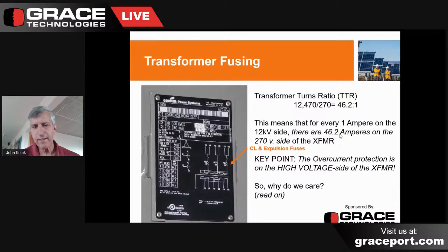Then there's a disconnect on there, which is the rotating switch that you operate with a shotgun stick. And then the important part I wanted you to see. You will see that there are 2 fuses in series with each other on the high voltage winding. One is called an expulsion fuse, and one is called a high current limiting fuse. Why I'm telling you this is that the expulsion fuses on a pad mount transformer only have an interrupting capability of about 1200 amps.